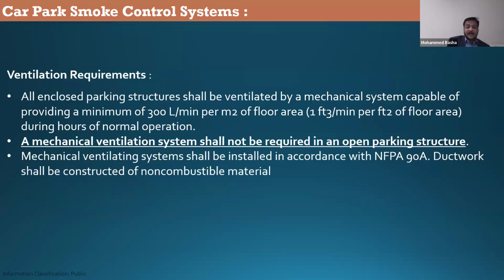Whereas if it's an enclosed car park, as per NFPA 88A, it requires a minimum flow rate of 300 liters per minute per square meter of floor area during normal hours of operation. Remember, NFPA 88A doesn't tell you to have a smoke extract system during the fire mode. It is we engineers who created that. NFPA says 300 liters per minute per square meter of floor area during normal hours of operation. They never say use 6 air changes, use 10 air changes for the fire mode. It is from British standards, BS 7346. This is what our QCDD is following.